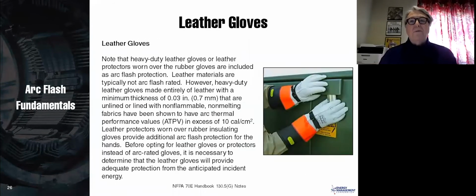Let's look at leather gloves. Leather gloves are not arc flash rated. And we've talked about arc flash PPE, and what we generally talked about was the balaclava and the harnesses and the face shield and the shirt and the pants and so on. Let's look at some of the other pieces of equipment. Note that heavy-duty leather work gloves or leather protectors worn over rubber gloves are included as arc flash protection. Leather materials, however, are not arc flash rated.